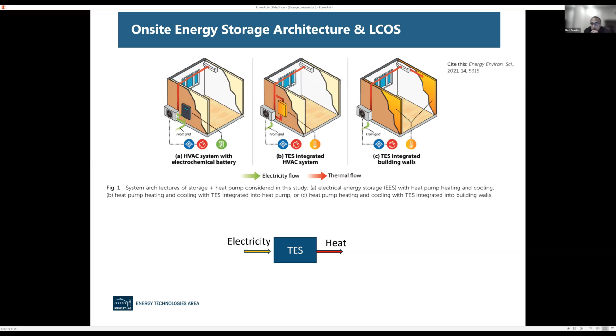There's so much area available. For example, in the US, a typical 2,000 square foot house can store roughly 44 ton-hours, which is about 150 kilowatt-hour of thermal energy storage. This is roughly equivalent to 9 hours of cooling, assuming 5 ton cooling is needed.